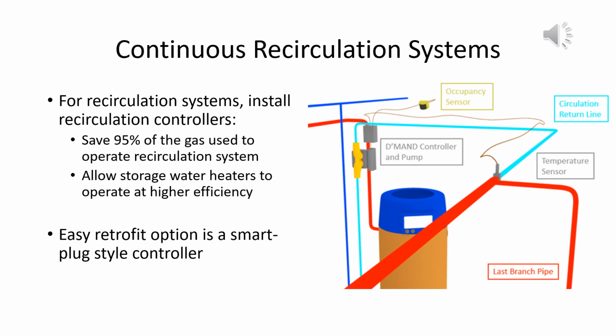Operators who have recirculation systems should consider installing recirculation controllers. They can save up to 95% of the gas used to operate the recirculation system and also allow storage water heaters to operate at a higher efficiency, thus saving energy. There are smart plug style controllers that are particularly easy to install.